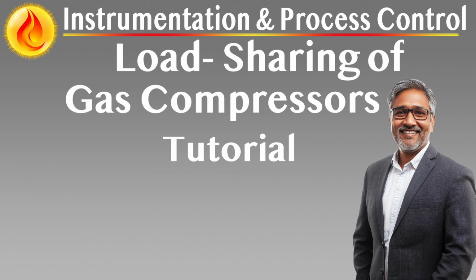Cold recycle loop integration. In systems with a common cold recycle line, a separate control loop modulates the cold recycle valve ahead of individual hot recycle valves. This anticipatory flow adjustment cools the recycle gas through a heat exchanger, avoiding thermal stress across machines. The cold recycle controller receives surge deviation feedback from all units and ensures early intervention before any single unit reaches surge.